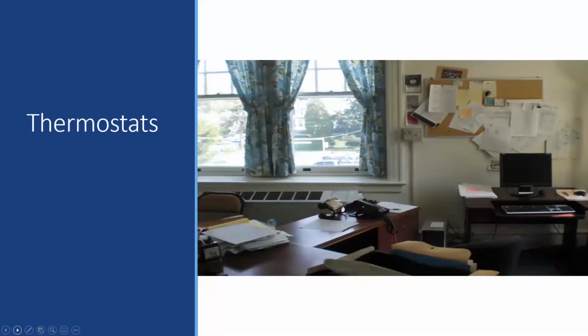Thermostats. Where are your thermostats located? How many thermostats do you have in your facility? Do you know what your thermostat settings are? Make sure that they're not close to a heat source or behind something that would impede their ability to sense the room temperature, such as a curtain. Thermostats need to be located on an interior wall, not an exterior wall, and also not in direct sunlight.